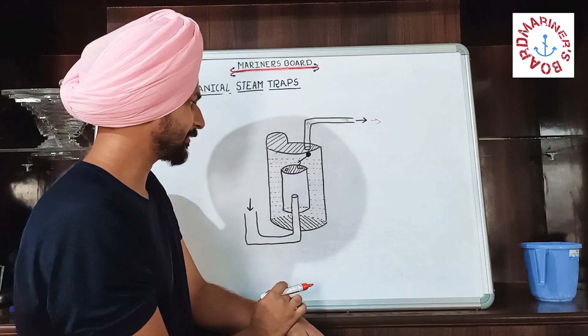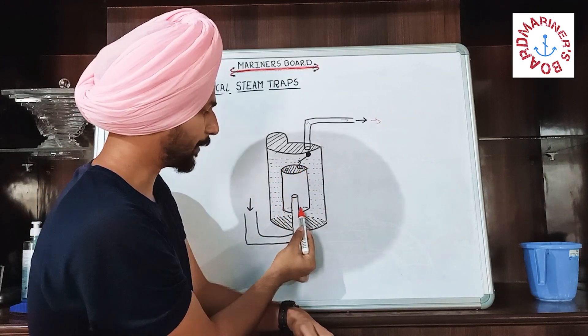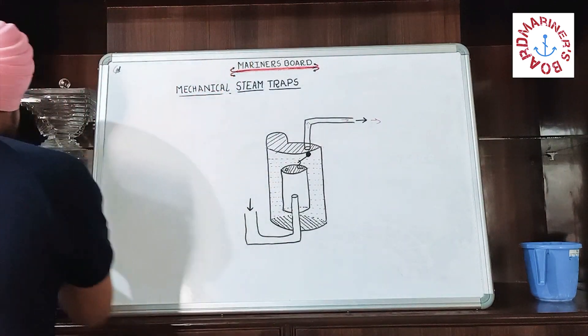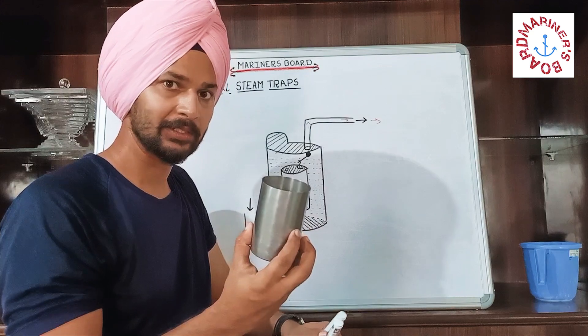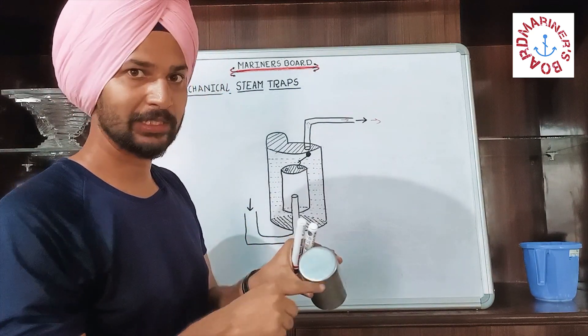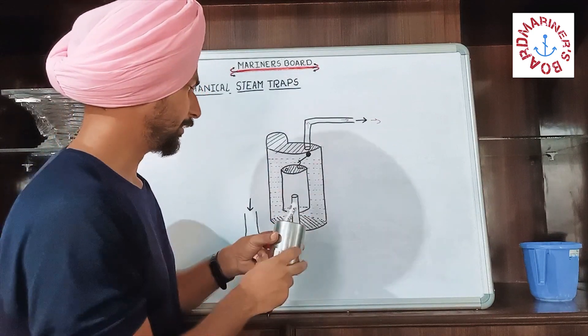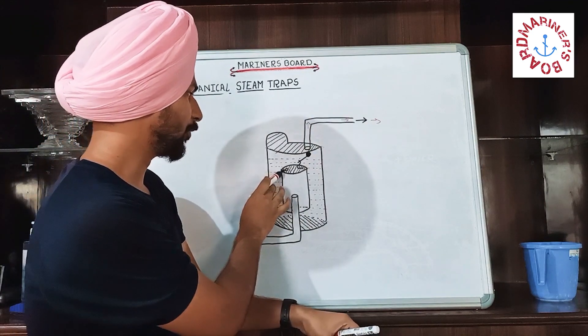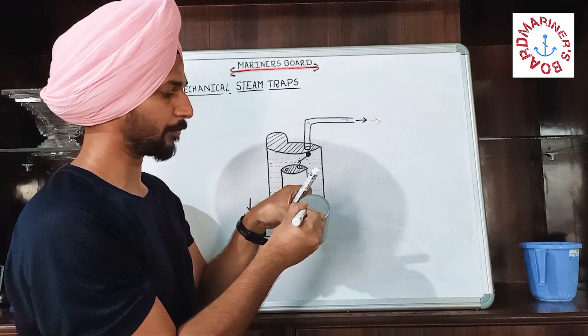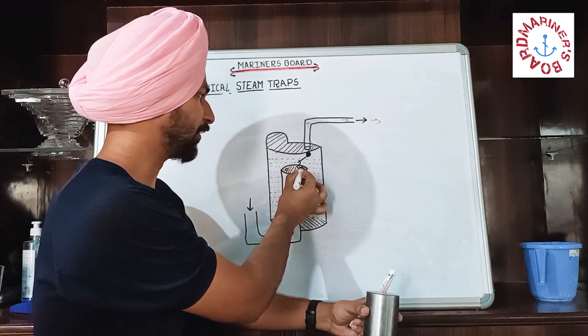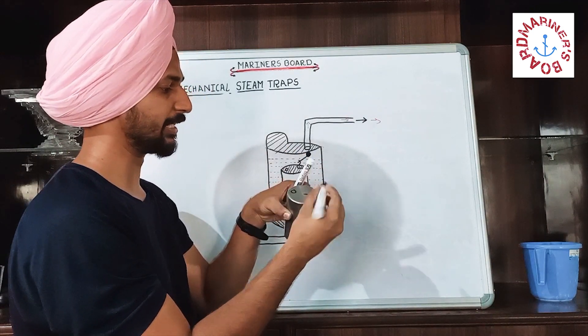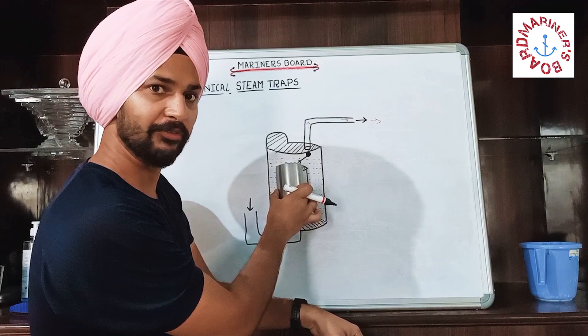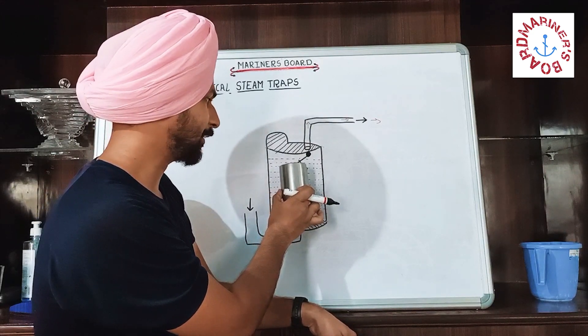This inner cylinder is closed at the top and open at the bottom, where the pipe goes inside. To make it simpler, it is similar to a glass where one end is open and the other is closed. The pipe goes inside from the open end. There is a hole at the top of the inner bucket, and the valve is attached to that hole. That is why it is called an inverted bucket steam trap — because the bucket is inverted inside it.